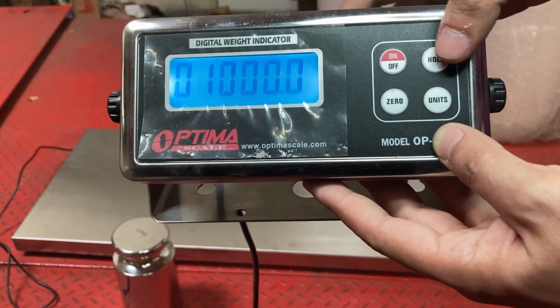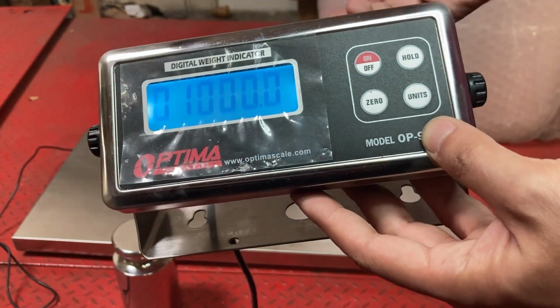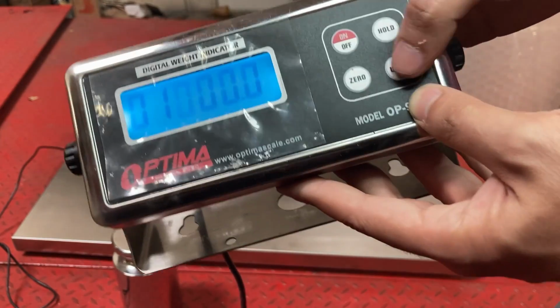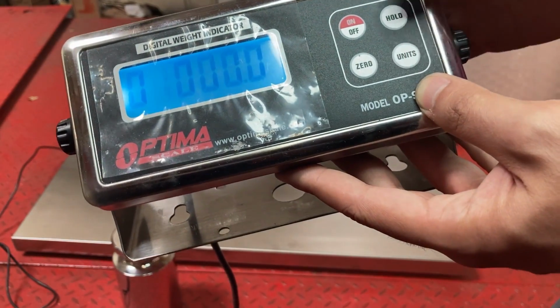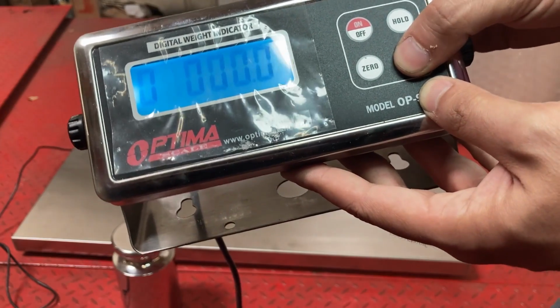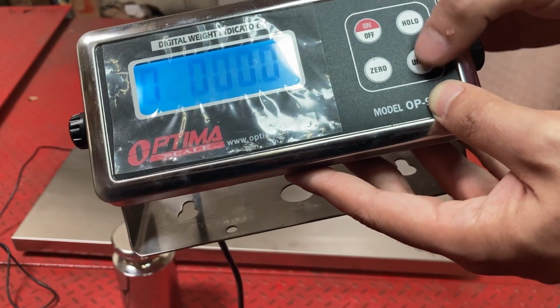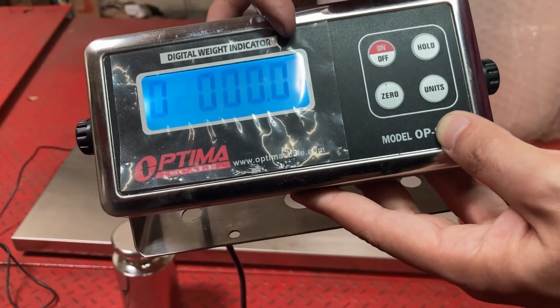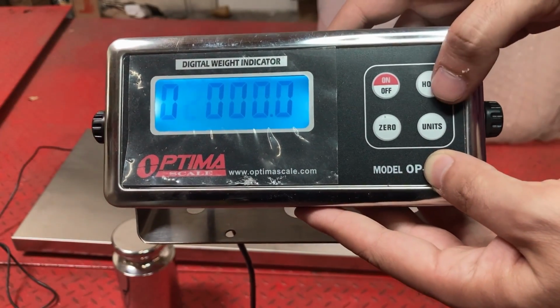So I'll press set. Right now it's set to 10,000, but it's not really important. That's the capacity, but you can see I can move left by pressing the 0 button, and the units button would decrement it. So say I want it to be 2,000. 2,000.0. It's okay. That's fine.